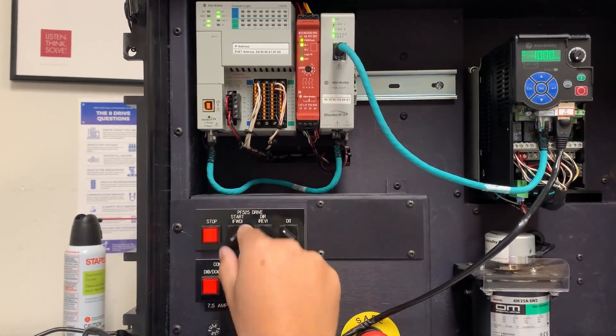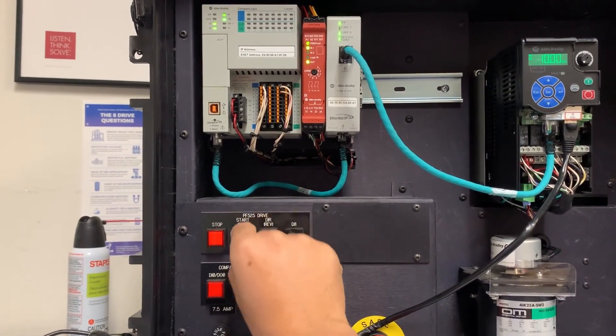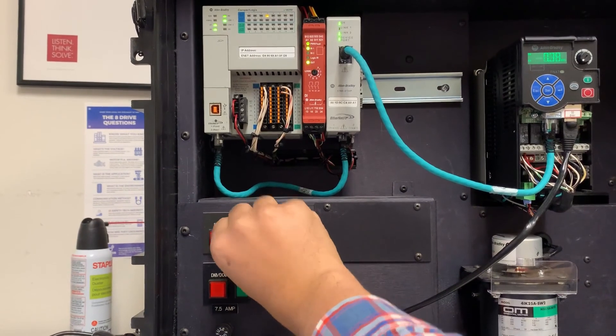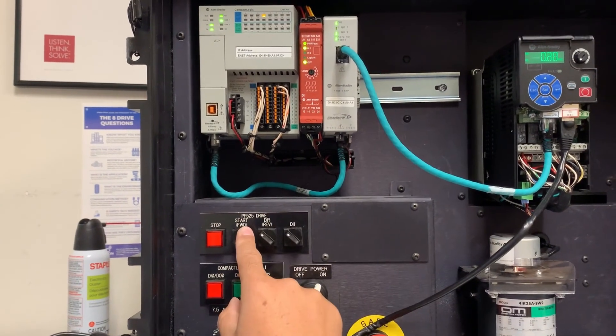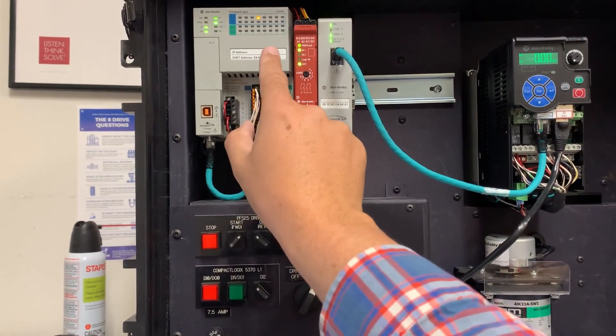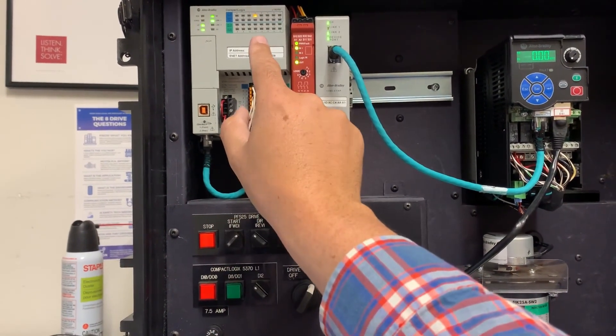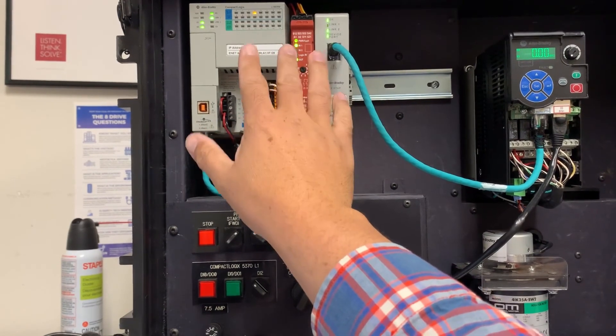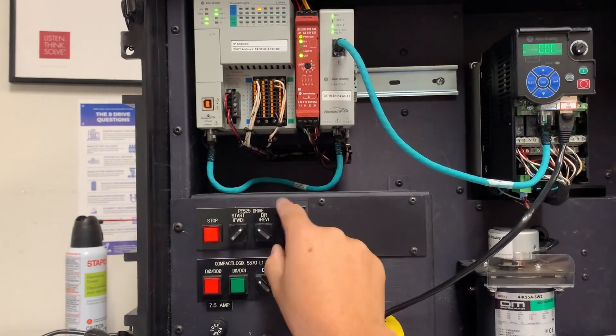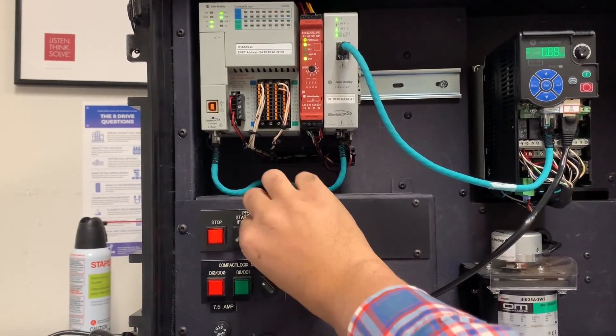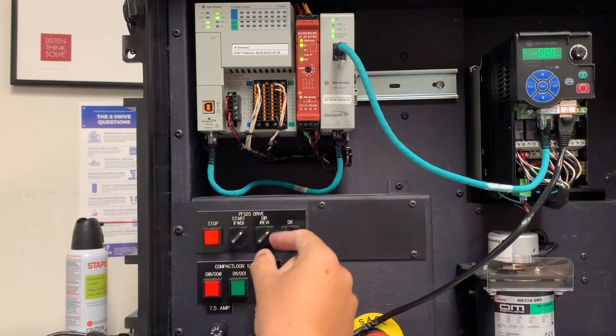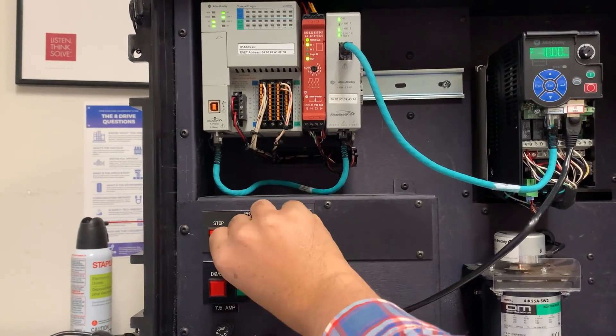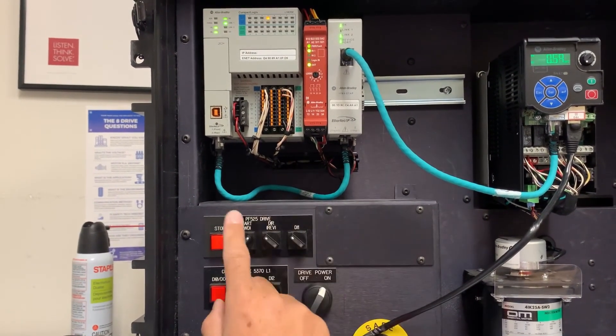That need only be momentary. I'm going to unengage the photo eye. I re-engage the photo eye. The drive immediately stops. A signal has once again been sent to the PLC to let it know that it can begin the dispense action. When the dispense action is complete, the drive starts to move again until the photo eye is once again engaged.